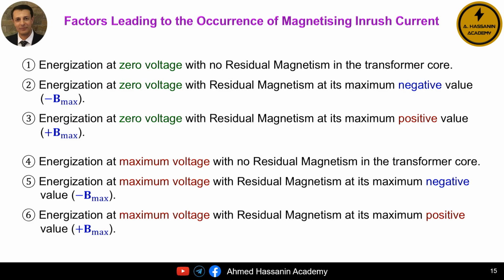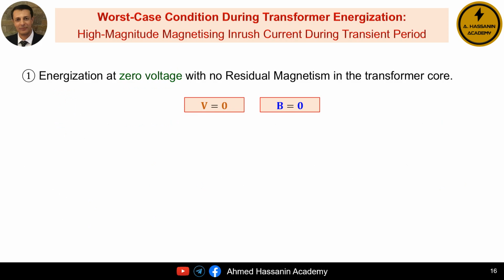However, in brief, we want to understand together what the worst case scenario is for energizing the transformer and what the best and most ideal condition for energizing the transformer is. In brief, the worst case scenario is the first case, energizing the transformer, or connecting the primary side of the transformer, when the voltage is 0 and there is no residual magnetism in the iron core. In this case, the transformer will undergo a transient period, resulting in a magnetizing inrush current with a very large value.